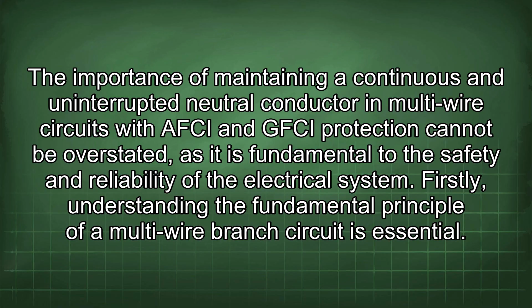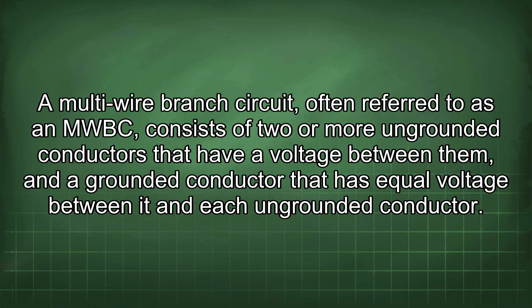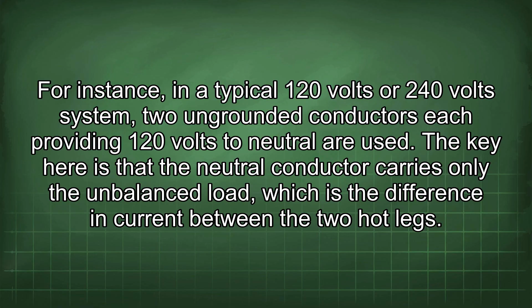Firstly, understanding the fundamental principle of a multi-wire branch circuit is essential. A multi-wire branch circuit, often referred to as an MWBC, consists of two or more ungrounded conductors that have a voltage between them, and a grounded conductor that has equal voltage between it and each ungrounded conductor. For instance, in a typical 120/240 volt system, two ungrounded conductors each provide 120 volts to neutral. The key here is that the neutral conductor carries only the unbalanced load, which is the difference in current between the two hot legs.